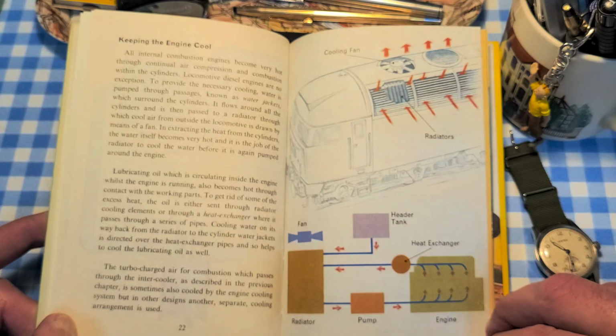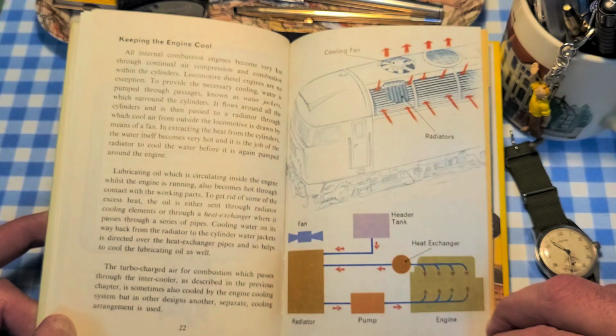Lubricating oil, which is circulating inside the engine whilst the engine is running, also becomes hot through contact with the working parts. To get rid of some of the excess heat, the oil is either sent through radiator cooling elements or through a heat exchanger, where it passes through a series of pipes. Cooling water on its way back from the radiator to the cylinder water jackets is directed over the heat exchanger pipes, and so helps to cool the lubricating oil as well.